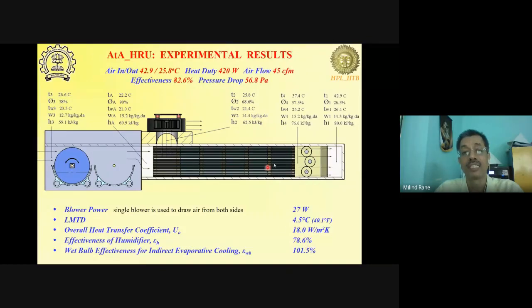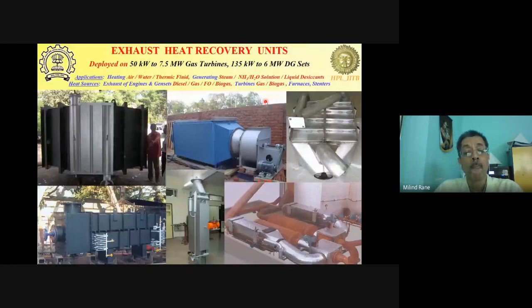And although we get such high effectivenesses, the pressure drop is very low. It is just 56.8 pascals. Typical pressure drops in conventional air-to-air heat recovery units are of the order of 150 to 200, or at times even 300 pascals. And all this using plastics.